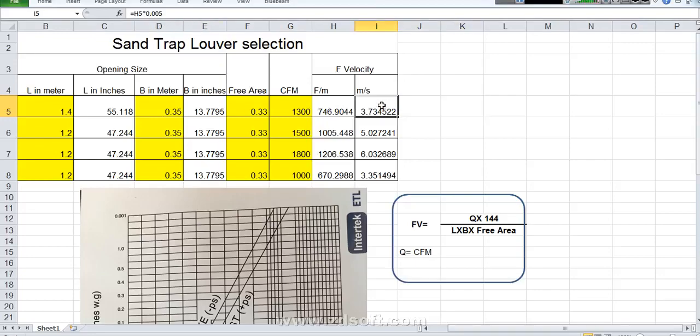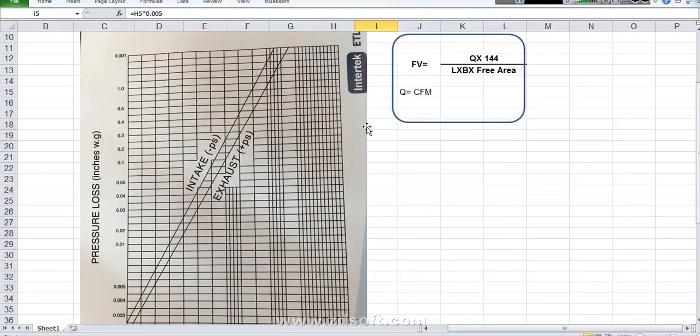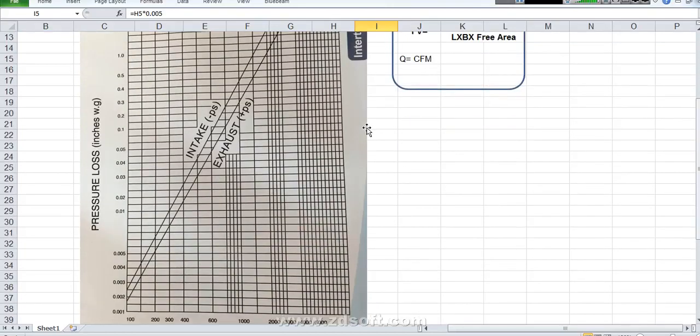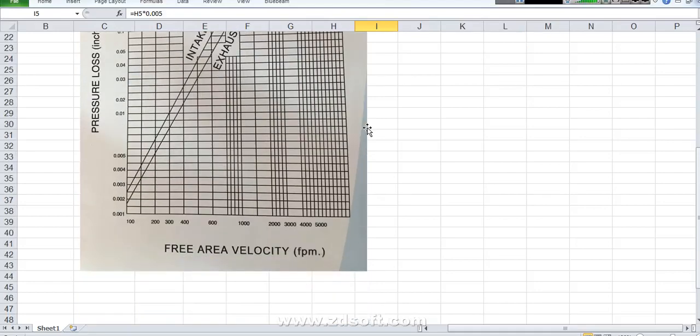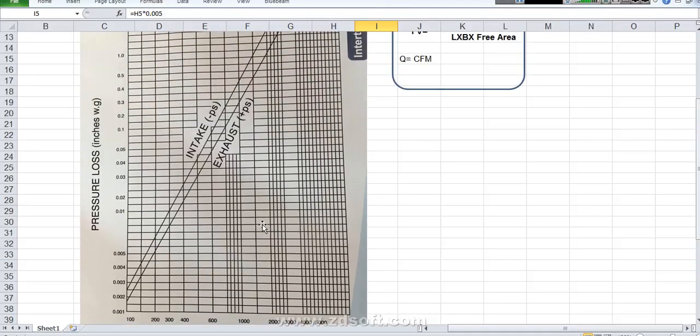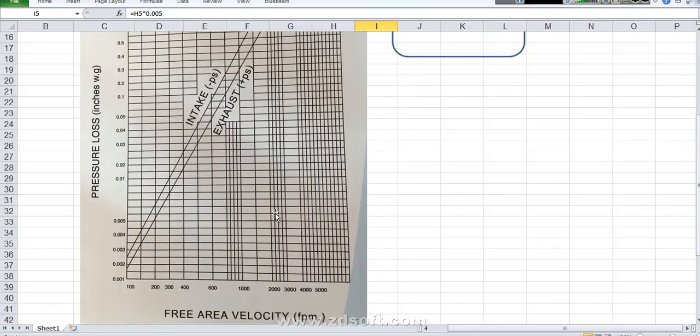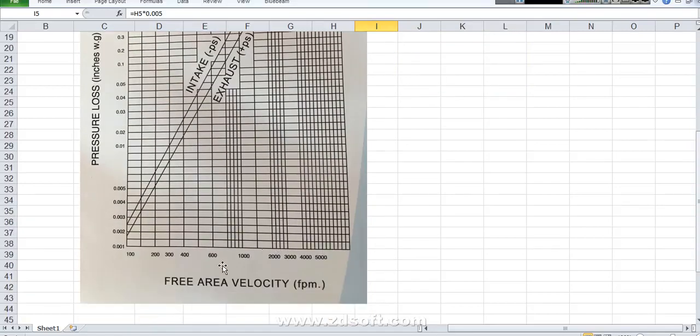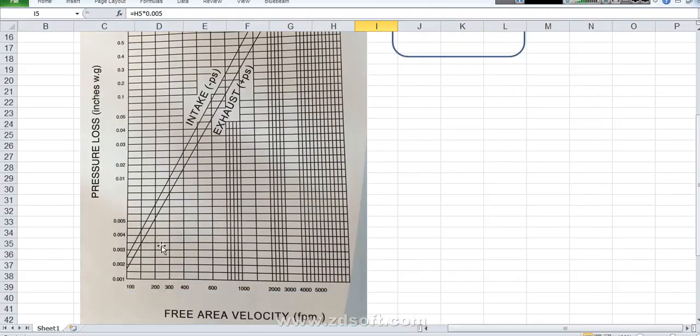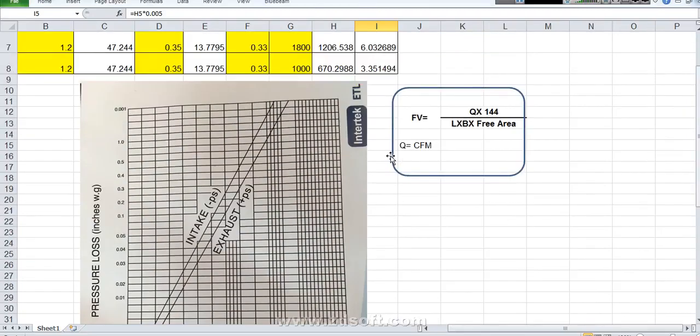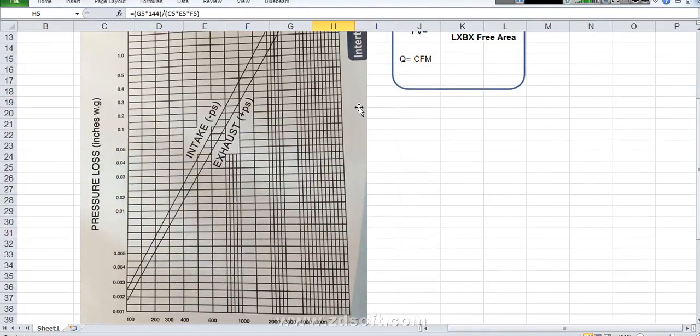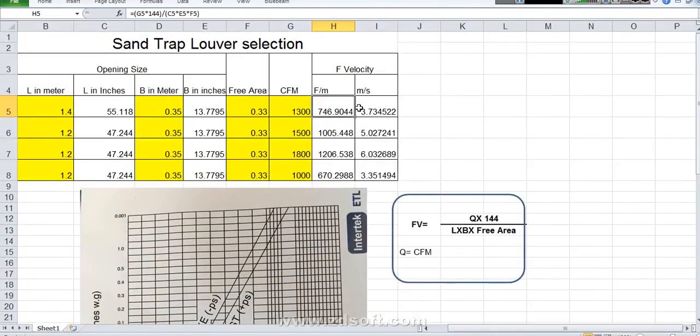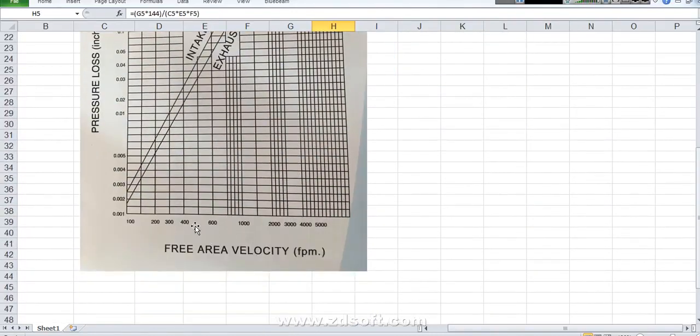Then in the manufacturer technical specification or manufacturer catalog you will find this kind of graph. This graph what it represent. This friction loss we can find out from this graph. For example here I got face velocity 746 feet per minute. Here we will go down. 746 is coming around here.